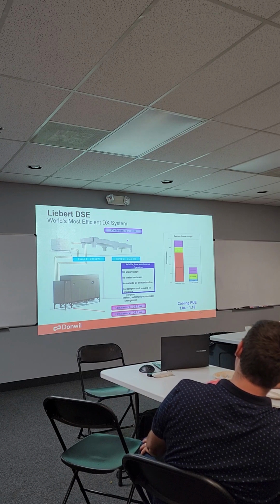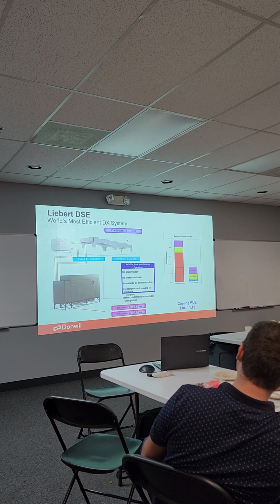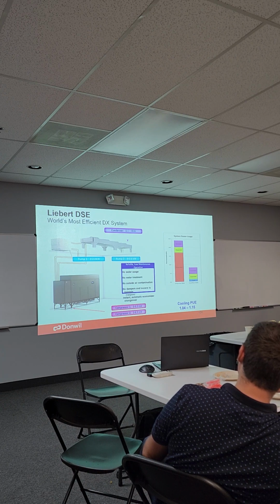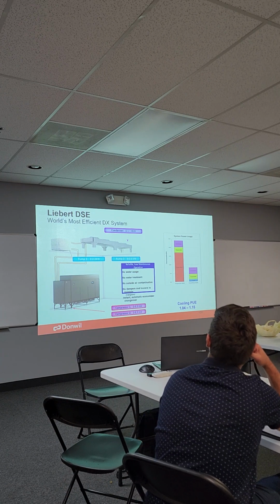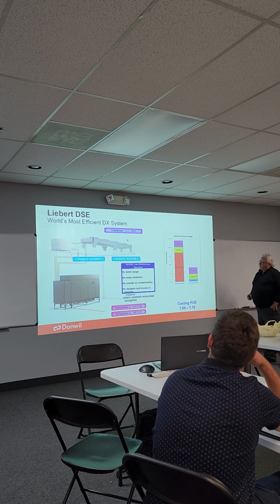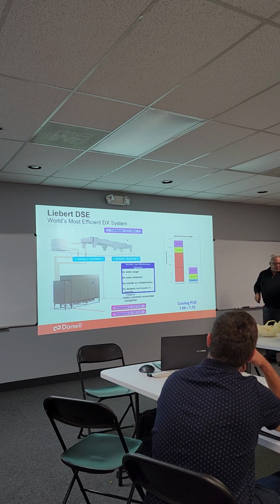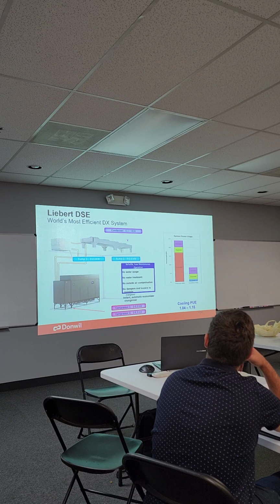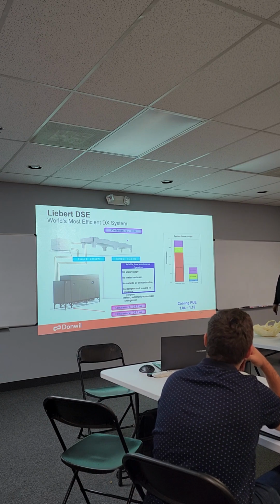So the DSE, we'll go a little more in depth here. No water usage, no water treatment, no outside air contamination. Remember we said we don't want outside air in a computer room. No dampers, louvers, or any of that stuff. Over here they're talking about the system power usage, I can give you this so you guys have it, I don't expect you to remember it. The thing to remember is this is a pumped refrigerant system that can start economizing below 65 degrees. And if you're in Cleveland, Ohio, how many nights do we go below 65 degrees, even in the summertime? Just a couple, just a few.